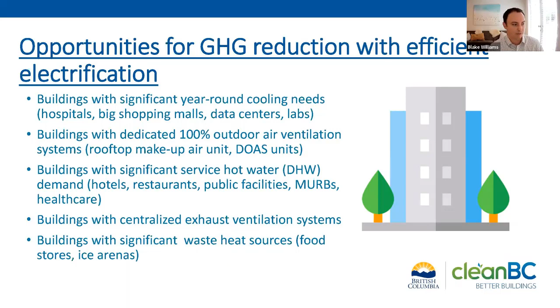The kind of projects we're looking for are typically found in buildings with significant year-round cooling needs - hospitals, shopping malls, large data centers, and the like. Also buildings with 100% outdoor air ventilation systems, where you're constantly conditioning outside air. We're also looking for opportunities with significant service hot water loads, typically found in hotels, restaurants, MURBs, and hospitals. Also buildings with centralized exhaust ventilation systems, and buildings with a lot of waste heat being rejected, such as arenas and food stores.